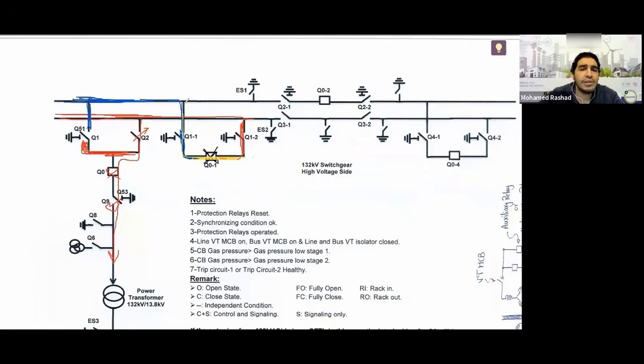Now the two voltages have become the same, so the voltage coming to you here, which is in yellow color, is now established. It goes around like this and goes here, then goes to the lower bar, loops through Q2, goes here, and reaches the terminals of Q1. So Q1 now has the same voltage before and after it, because the two bars have now become a single piece, having been closed together. The two bars are now aligned and they remain the same, having become the same wave, the same single wave. In this case, if you close Q1, you won't have any problem because there is no voltage difference across the terminals of your disconnector switch. All right? So in this case, what do we call it, engineers? We call it load transmit.